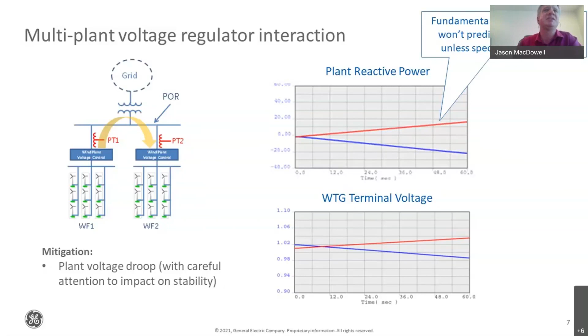So the best practice is to make sure we understand what's around us from the interconnection of one plant, and if there are multiple plants around, it's very likely that we will need to coordinate those multiple plants with voltage droop at the interconnection and at each plant control, reflecting that mitigation as early as possible in the models and as early as possible in the interconnection process as you're applying for a new plant to be connected. Testing the mitigation of the voltage droop is a very good practice, and ensuring that the coordination of the controls is done adequately throughout the interconnection process, including validation of the models, is going to be key. So with that, I'd like to wrap it up and ask for any questions, and if not, I'll hand it over to our next speaker.